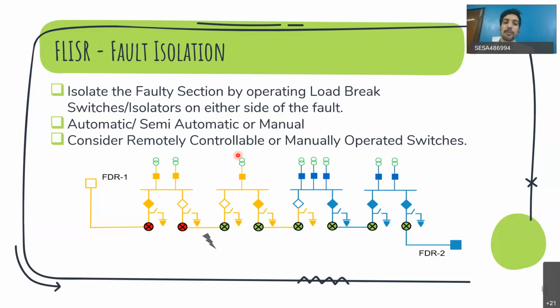Here you can consider remotely controllable or manually operated switches. For example, you have so many RMUs. Say this RMU is remotely controllable, so it is reporting to the control center, but here there is no communication equipment, so this one is not reporting to the control center and you cannot remotely operate it. But still, you can use this isolator to isolate the fault by sending the field crew there and asking him to operate it manually. In that case, outage time will increase. To avoid that, if the next RMU is remotely controllable, you can immediately open that. Then some more people will unnecessarily be under outage, but the people belonging to the non-faulty section will get restored immediately. Based on the requirement, the operator can take a call in this case also. That is the second step, fault isolation.